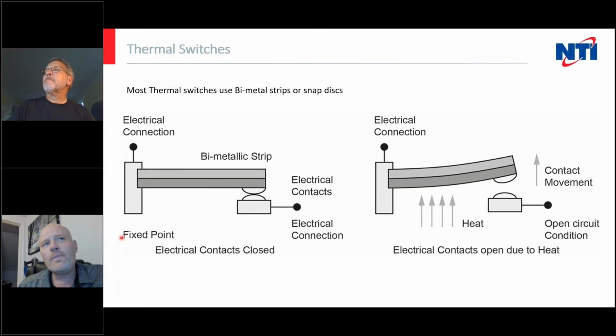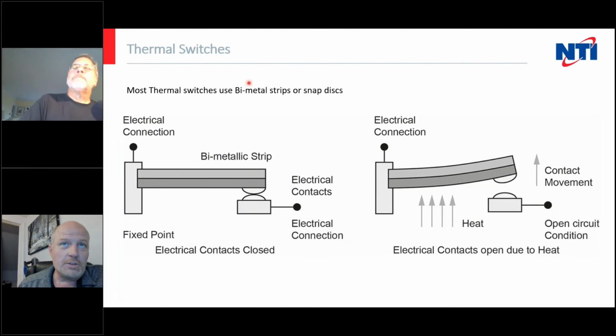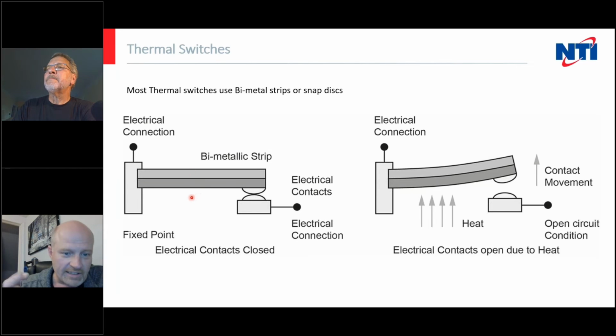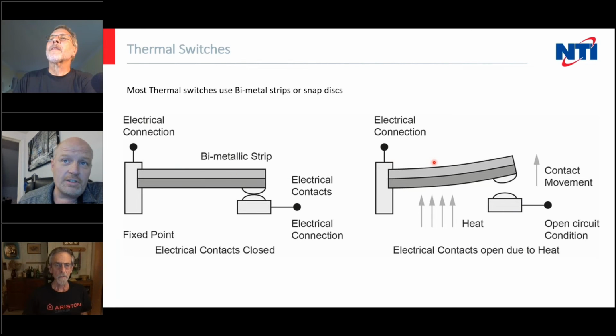So, all right. The other thing we use a lot is thermal switches. Most thermal switches use a bimetallic strip or a bimetallic disc. And these work basically, there's 2 different types of metals that are bonded together. As you heat them, we all know that things expand when they get hot and contract when they get cold. Well, bimetallic strips are designed so that one side expands or contracts faster than the other. Basically you add some heat, and eventually the side that expands more, in this case the dark gray, opens the contacts and trips the thing open.